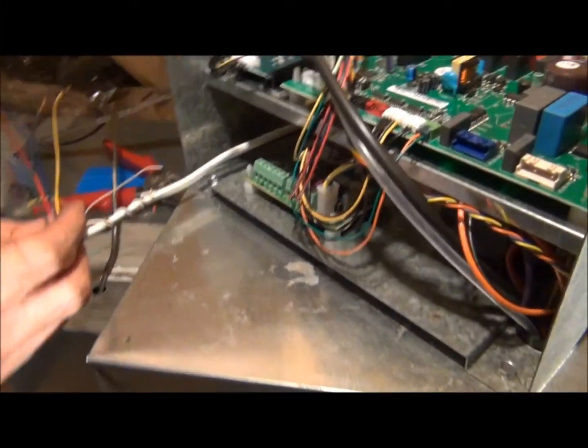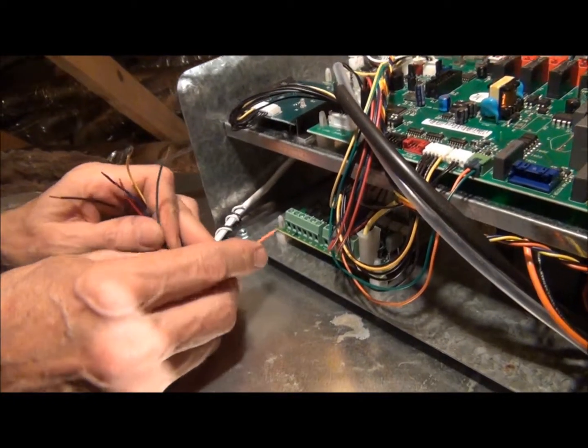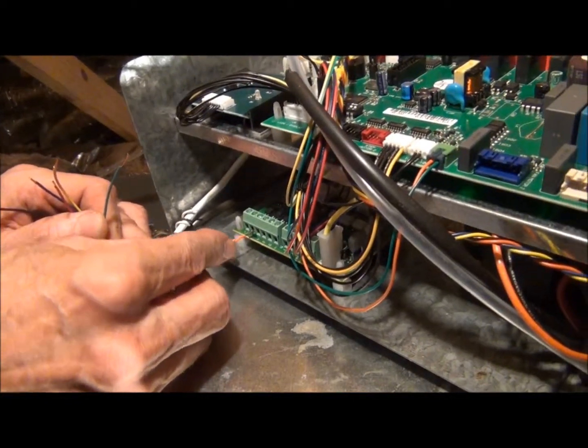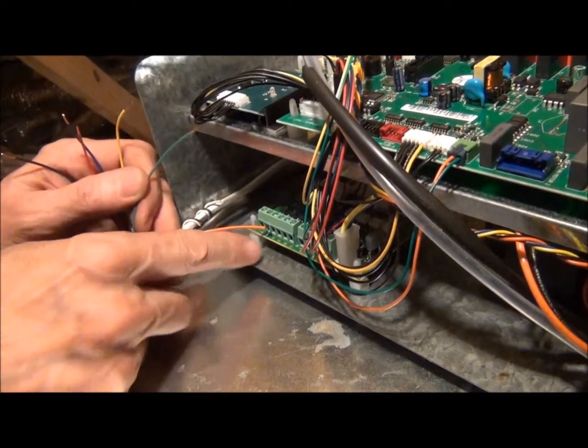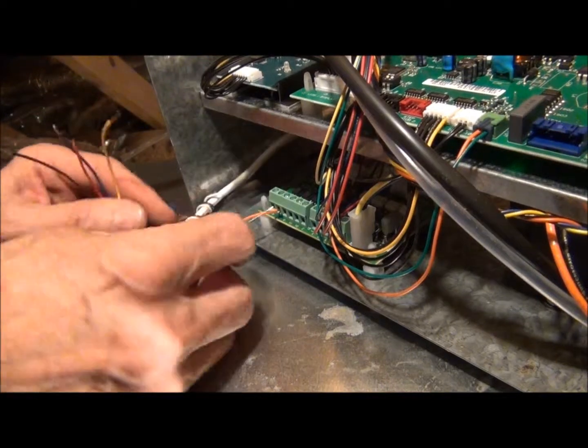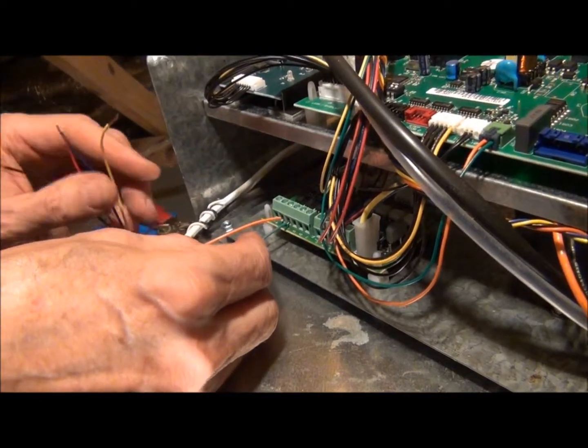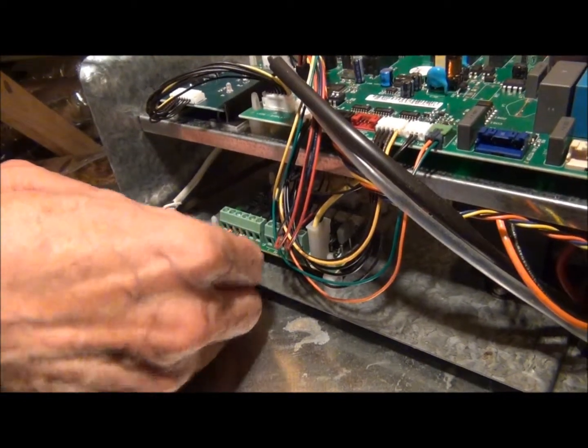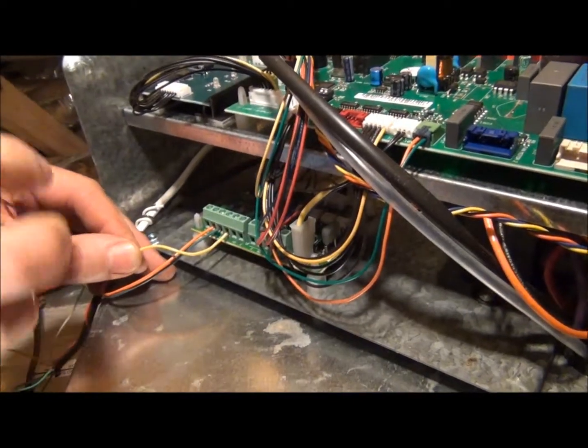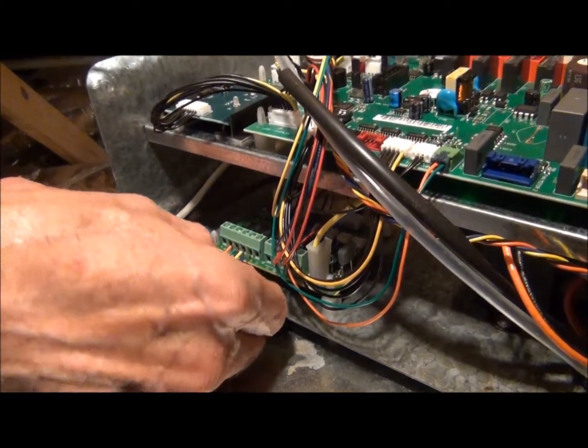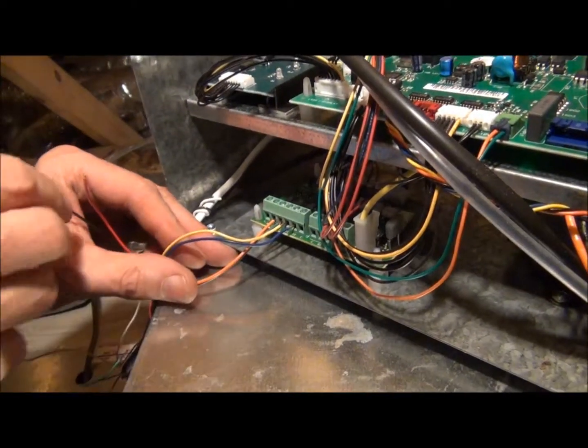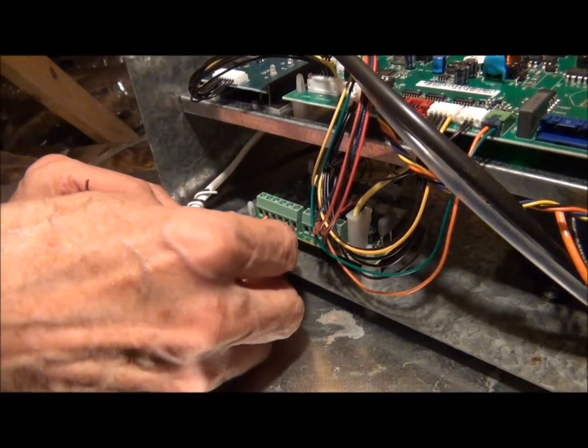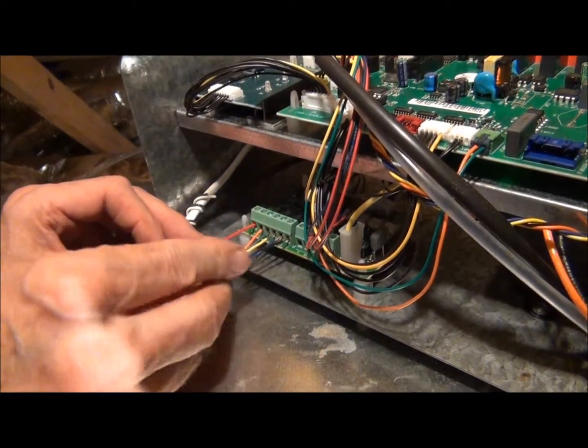For field wiring, we have our thermostat wire. We use B even though this one says O, and we have G using green. Then we have Y1 for stage 1, and blue for Y2 stage 2 heat pump and AC. We're using black for common and red for hot.